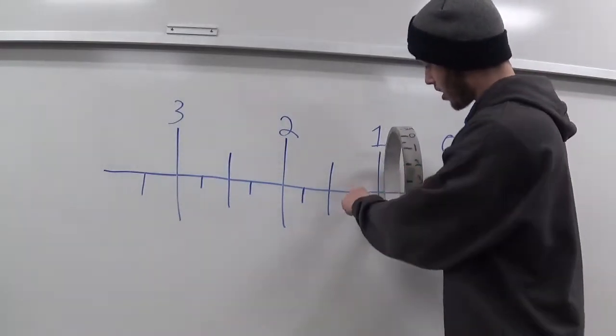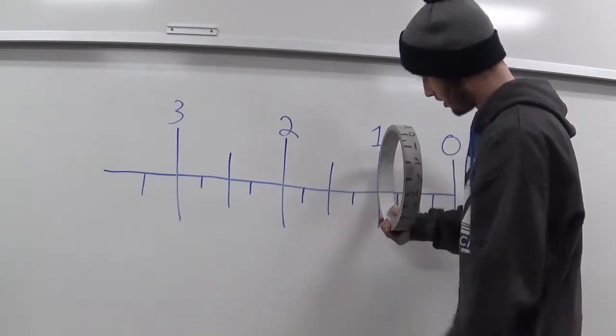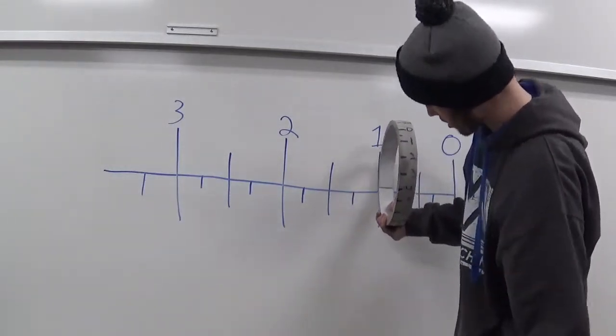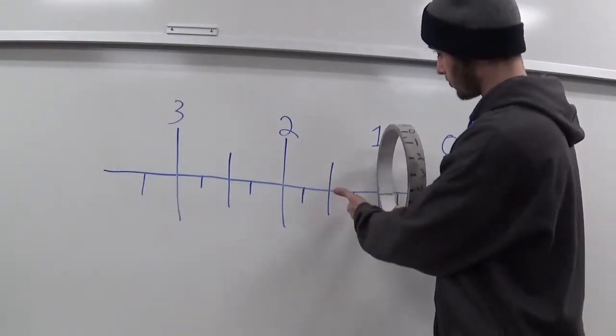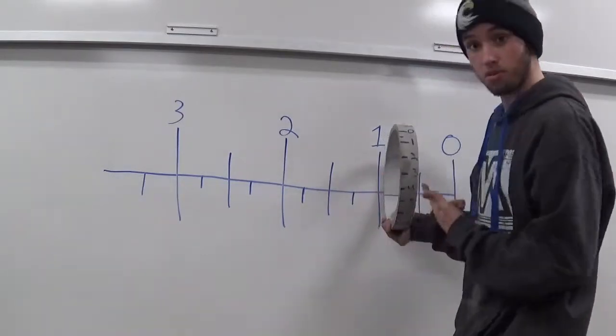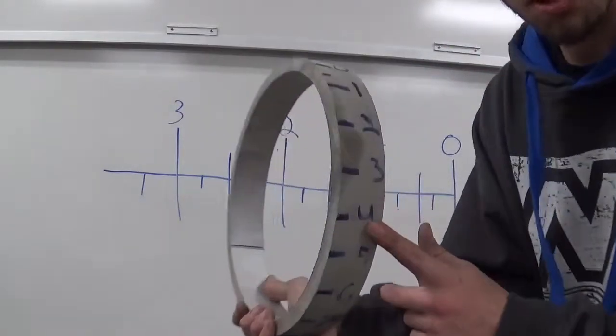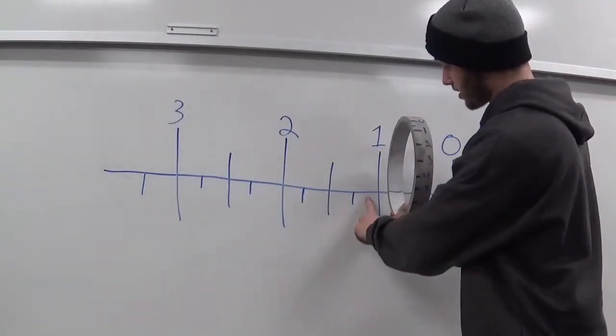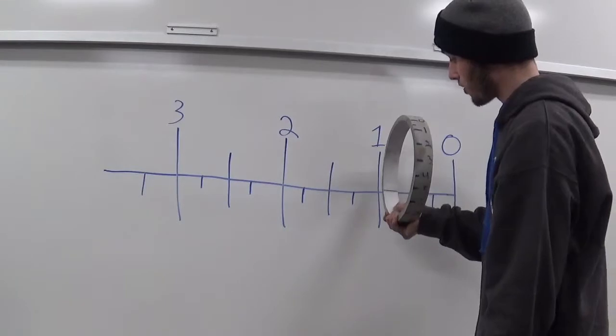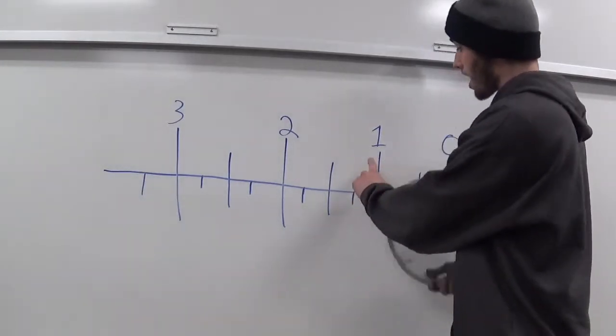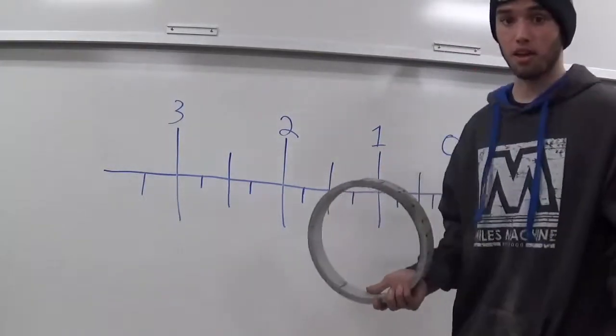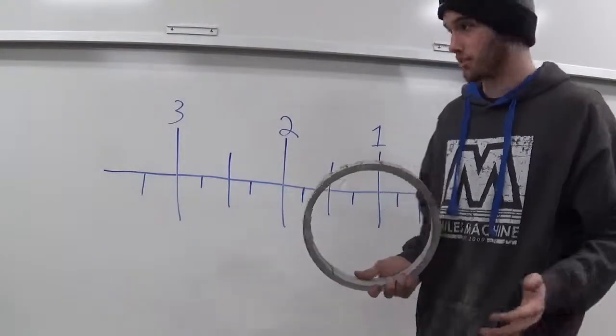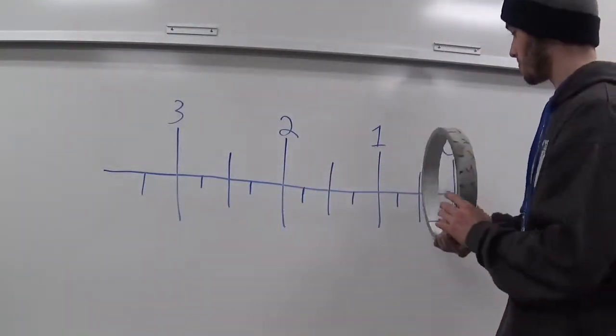Now I'm looking for whatever number best lines up with this center line here. So here I'm going to say this three, this number three here—I hope you guys can see that good—three lines up best with this line, so that's letting me know that I'm three thousandths past the 100. So that's telling me I have 103 thousandths.